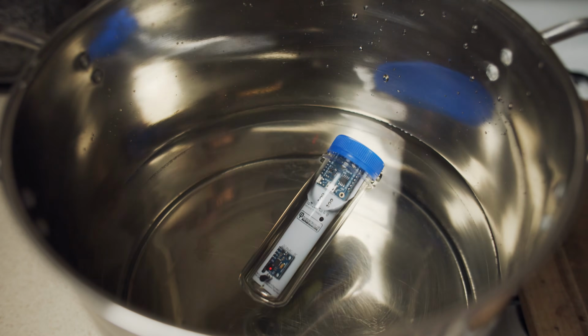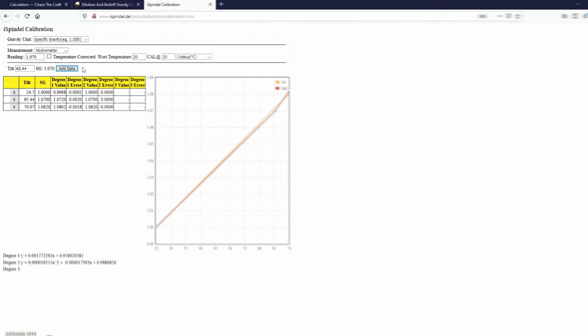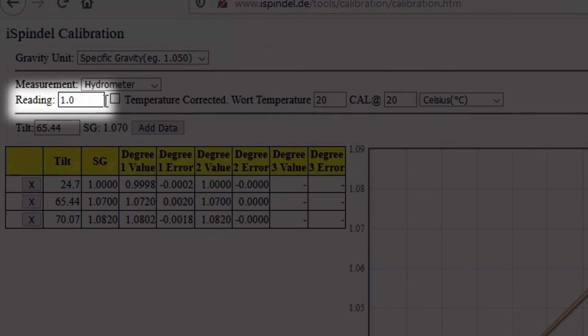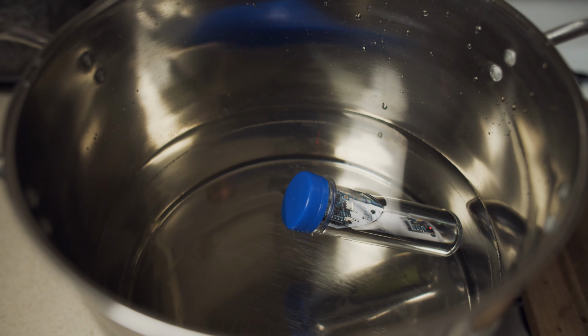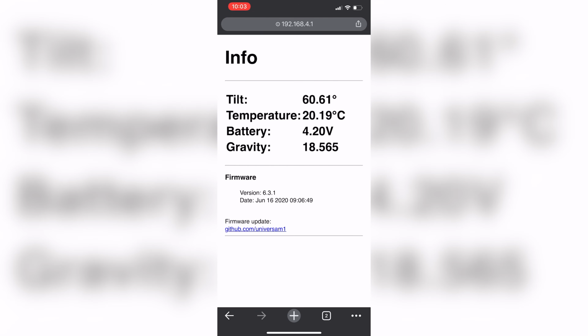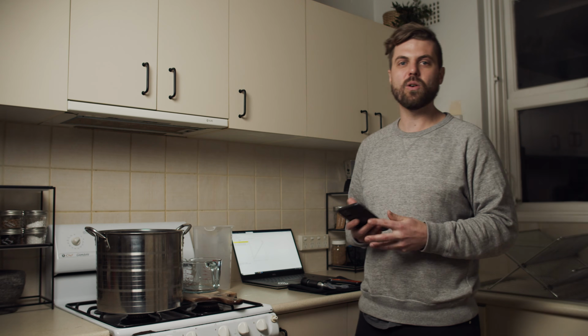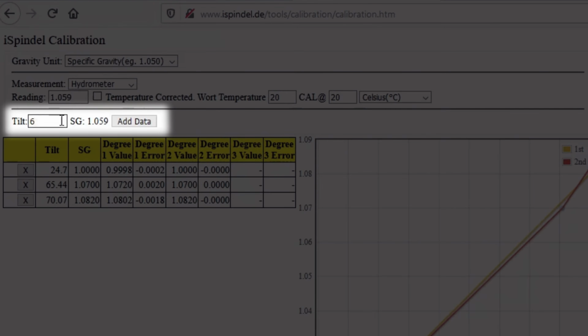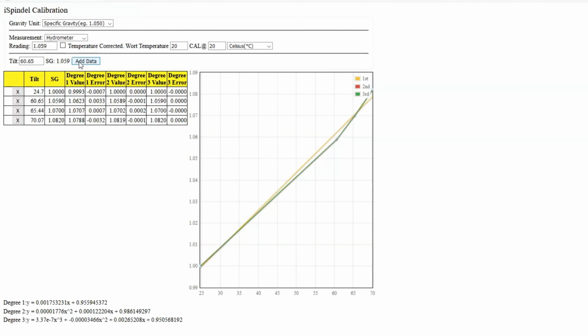And while that's settling out a little bit, I'm just going to go back into our calibration tab, change the reading to 1.059. We'll let it settle down before we get the tilt, and we'll add that value to the table. Okay, so everything's settled out there now. I'm getting readings in the 60.6s, so 60.61, 60.70, 60.62, 60.66, 60.66, so 60.65. So I'm going to call that 60.65. I'm going to add that into our tilt value. Okay, we're going to click add data there, and as you can see, another point on the graph.